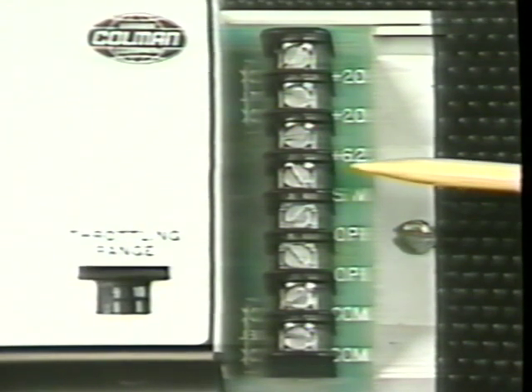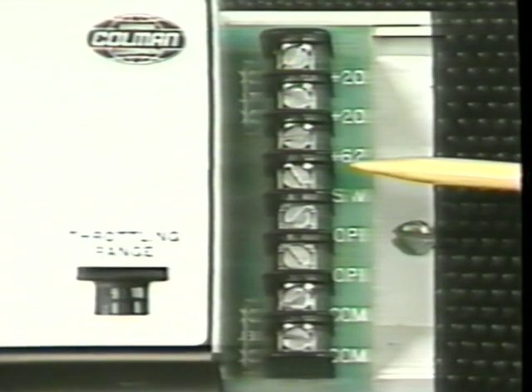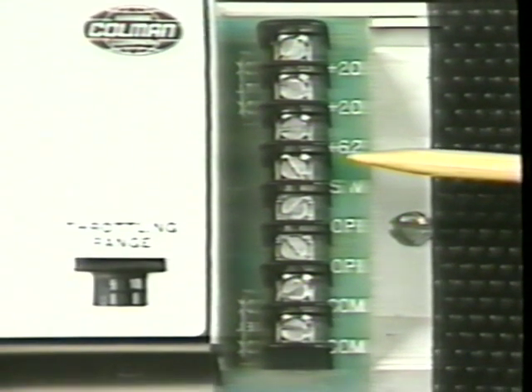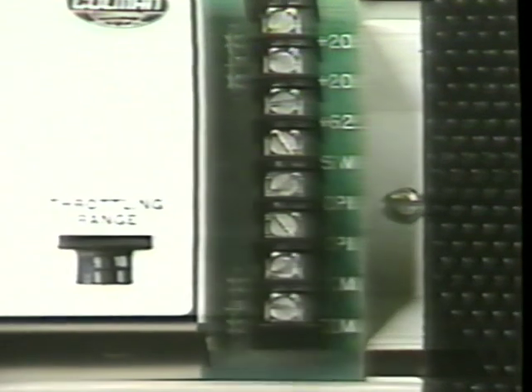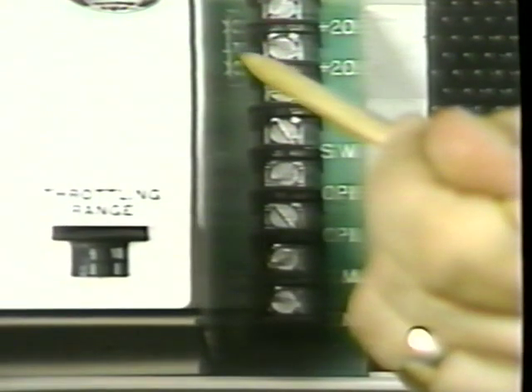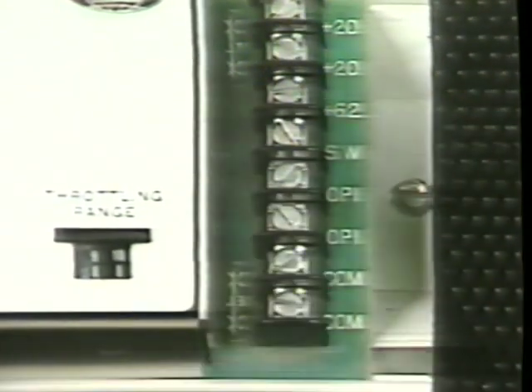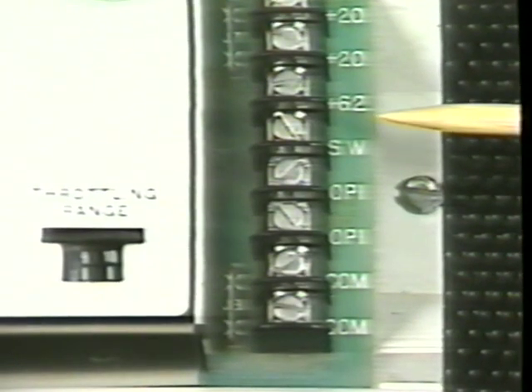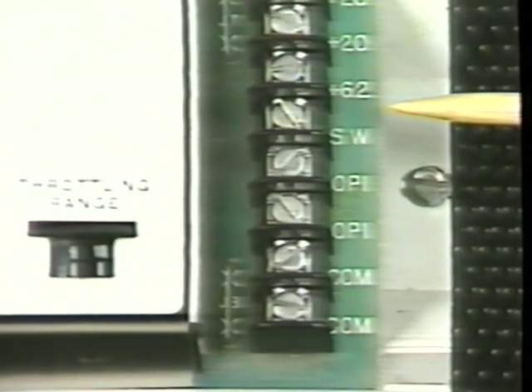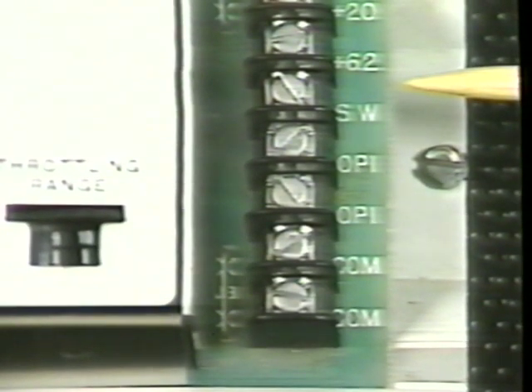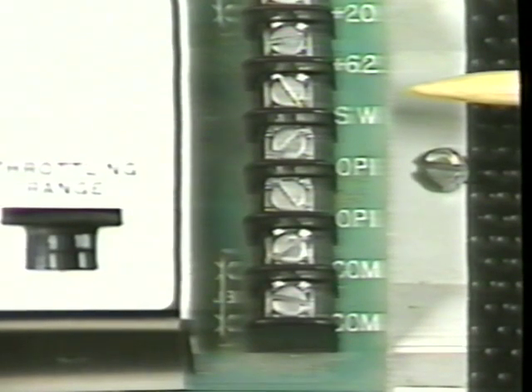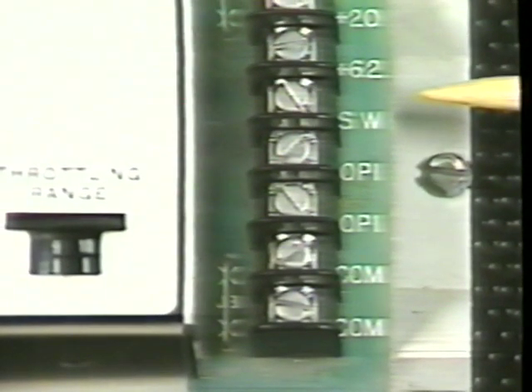SW. This is the same as the +6.2 terminal, but can be isolated by cutting jumper strap J7, visible here. It functions then as a summer-winter switching terminal, with the switching of the controller action from direct to reverse acting and back based on some specific condition. An example of this will be given later.